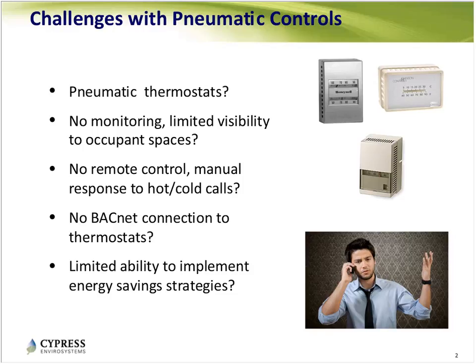They do control temperature well, very robust - it's amazing that 100-year-old technology is still in use in some of our most prestigious buildings and still keeps people comfortable. But compared to modern technology, you have no monitoring and limited visibility if anything goes wrong. So if a damper gets stuck, or somebody gets too hot or too cold, people call in and complain, and then you have to go fix it. Compared to a modern digital system, you have alarming and trending - you detect problems before people become uncomfortable. That's a major shortcoming of pneumatic controls, because you don't get that visibility.